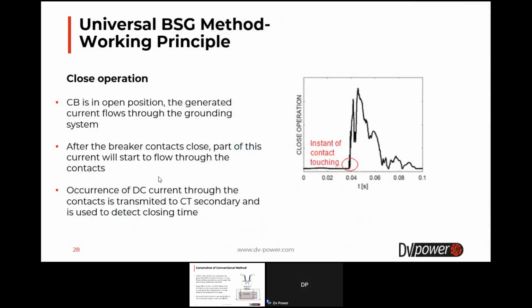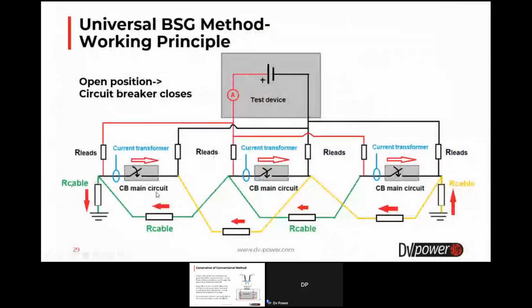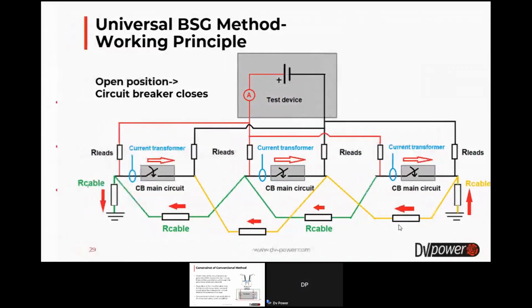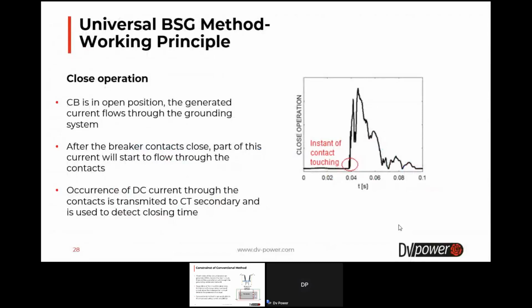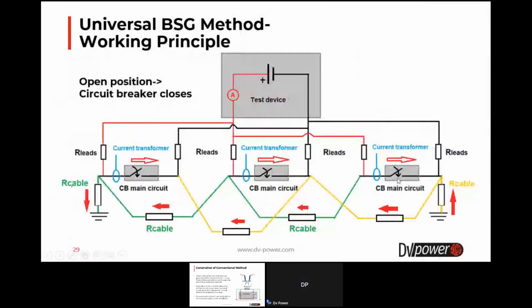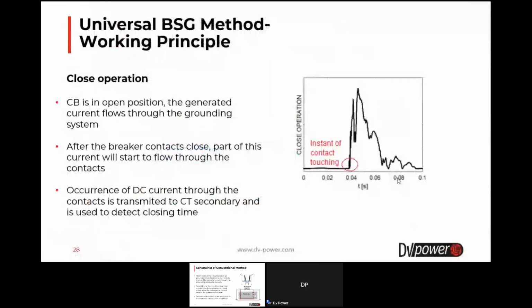So let's consider a closing operation first. Let's say the circuit breaker is in open position and the generated current flows through the grounding system only, as can be seen in the following slide. If the circuit breaker is open, the generated current from the test device flows through the grounding system and grounding cables. After the circuit breaker contacts close, part of this current will start to flow through the main circuit of the circuit breaker, as can be seen here. That change of the currents, or the occurrence of this DC current through the contact, is transmitted to the current transformer secondary, and that signal is used to detect the closing time. An example of that signal is shown in this figure. So the instant of the appearance of the signal at the current transformer secondary is the instant of the contact touching.